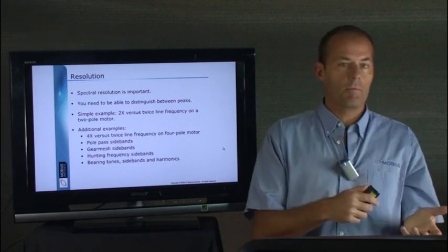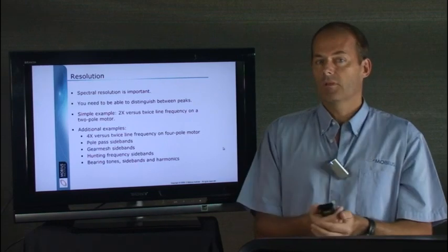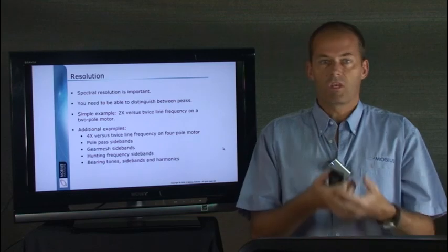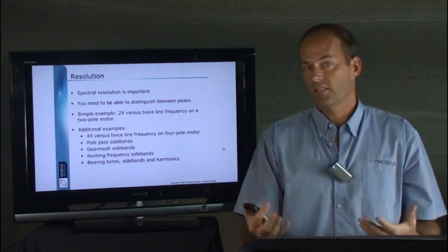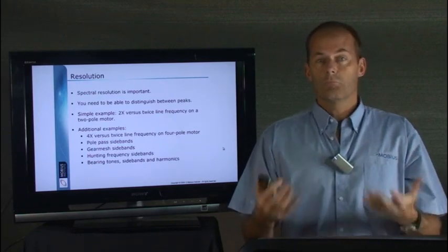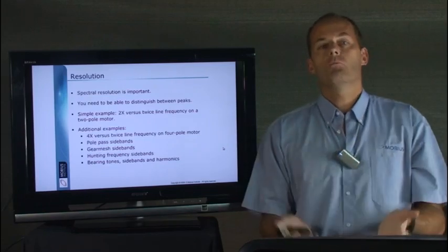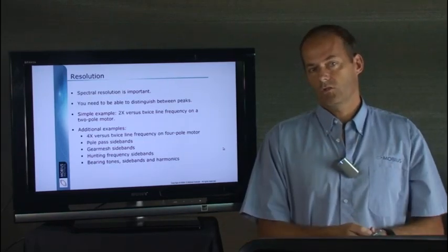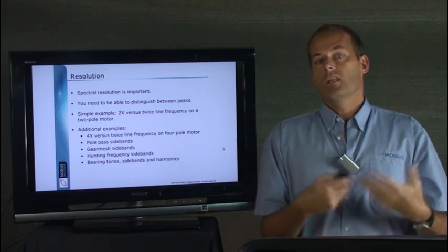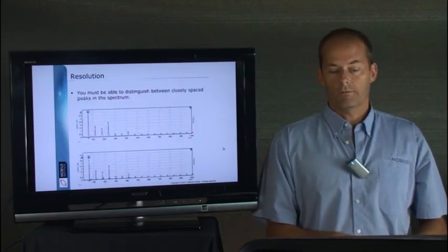Now, a long time ago, the issue with resolution was either the instrument capability or memory. Higher resolution measurement, when we go from 800 lines to 1600 lines to 3200 lines in a spectrum, takes more memory. But I hope that most of you now have analyzers with a lot more memory, so that shouldn't be an issue. But what most people don't realize is that by increasing the resolution, the measurements take longer. And that's the point I want to address here.